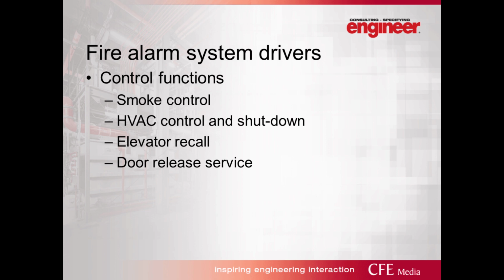The last thing that might drive fire alarm systems is when we have other features in the building that require a fire alarm system to control them. Smoke control is a good one, right? We might have a three-story building with an atrium that requires a smoke control system. So generally we would have a fire alarm system to activate that smoke control system. The building otherwise may not have a requirement, but the design feature could drive that requirement. We do have HVAC control and shutdown requirements depending on the size of the systems that are present, right?